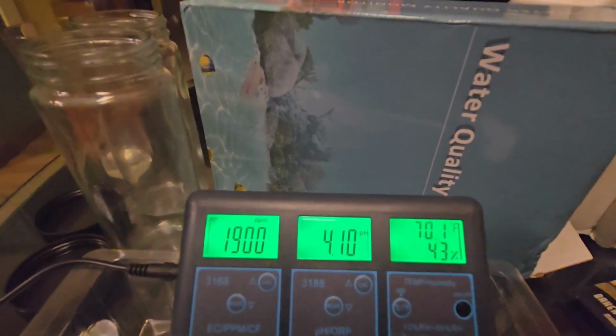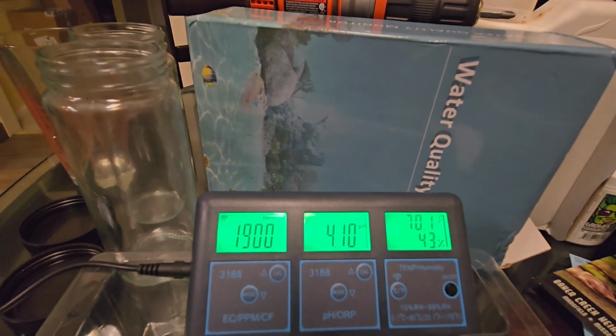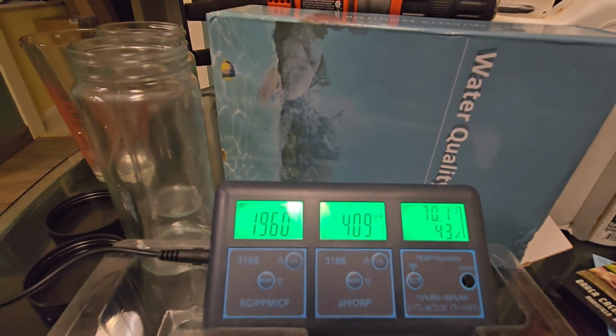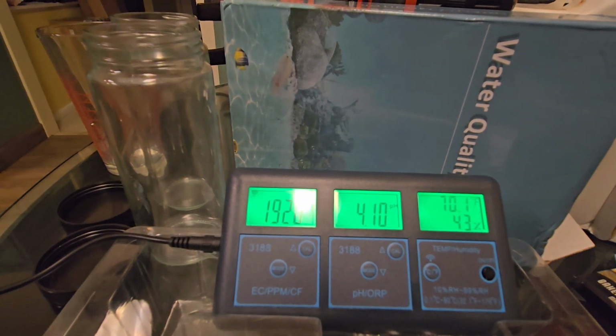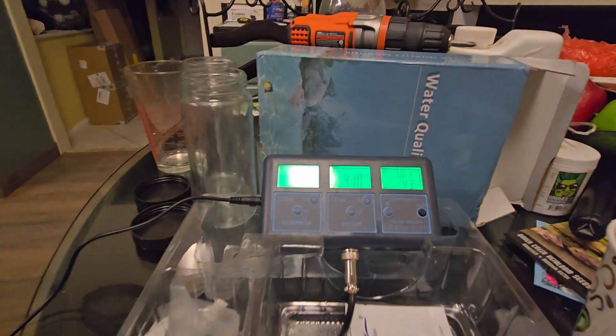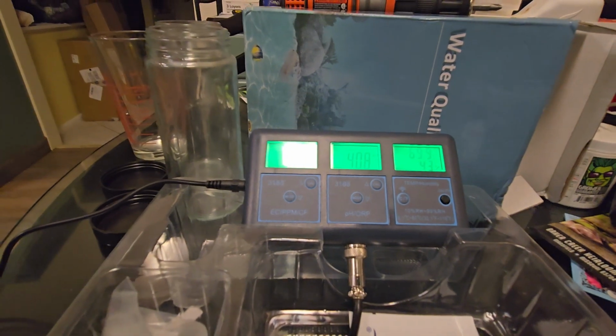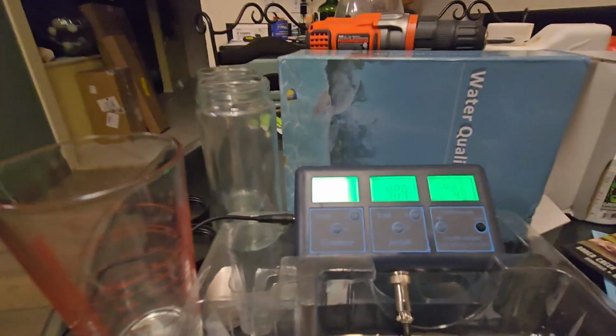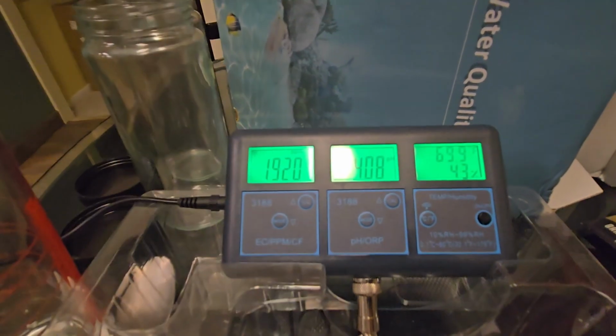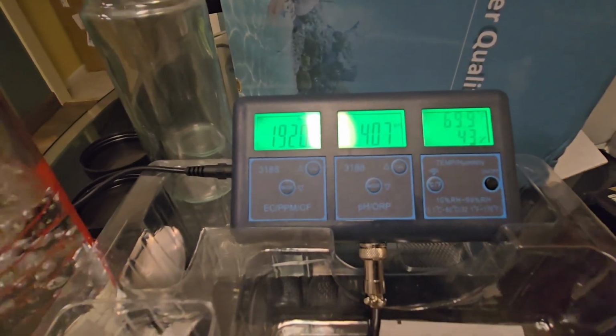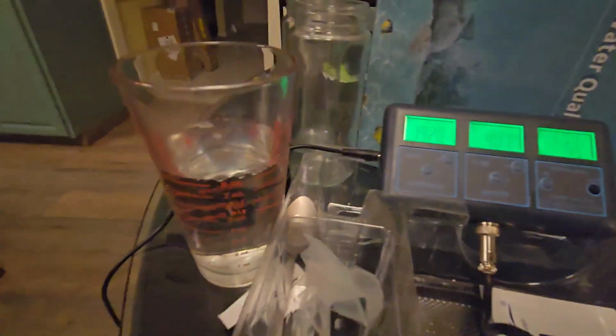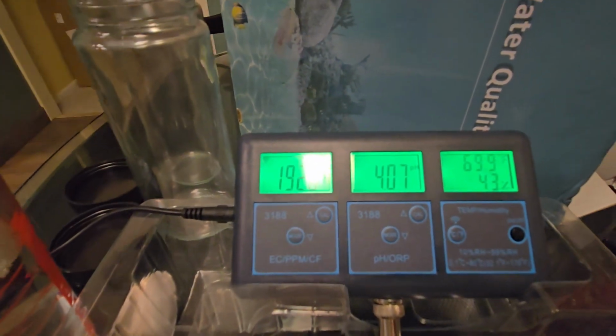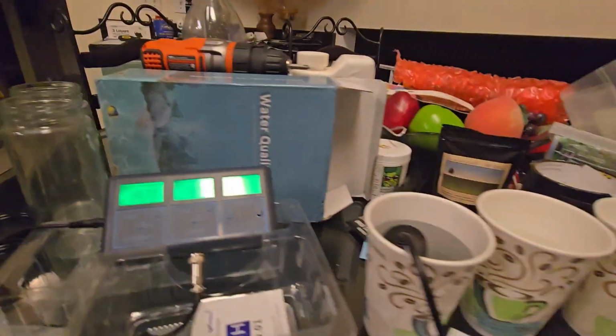So right now, based on what this is saying, my calibration solution looks like it's showing a little bit high at 410. Let me go ahead and get clean water poured into another glass so that we can rinse that. I'll put that here. And just using some distilled water in my measuring cup to rinse that off with. I'm going to go ahead and just move that probe around a bit more.